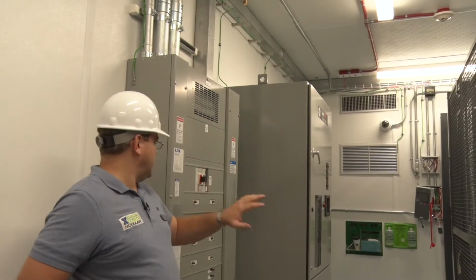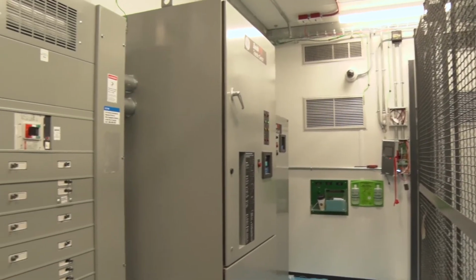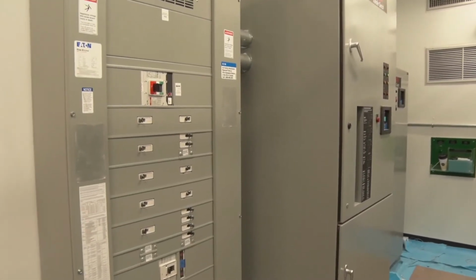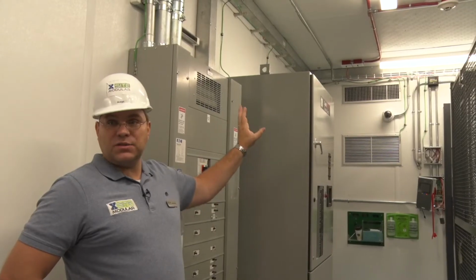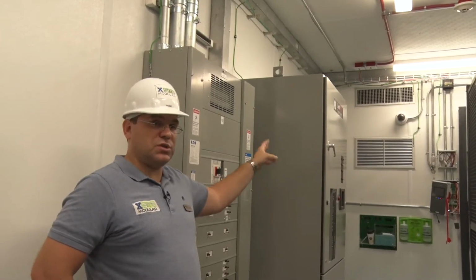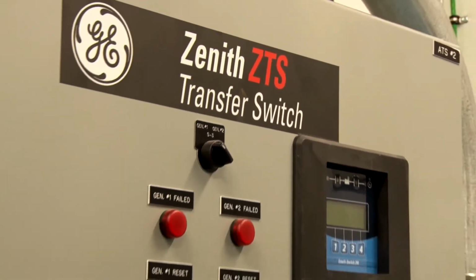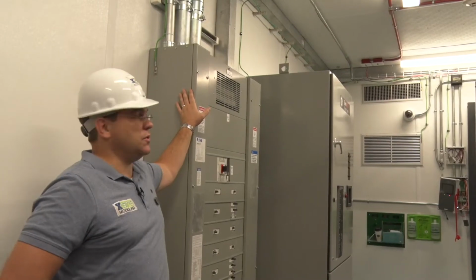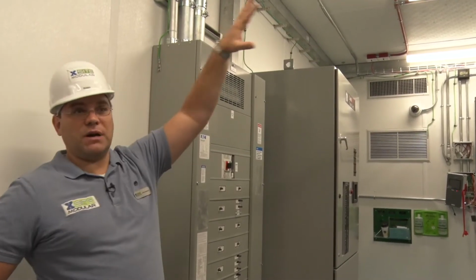You've got in here the AC switching equipment, which will switch between utility power, generator power, and in this case there's 2 generators, so it will also switch between generator A and generator B. You've got your main distribution panel, which distributes the AC power throughout the building.